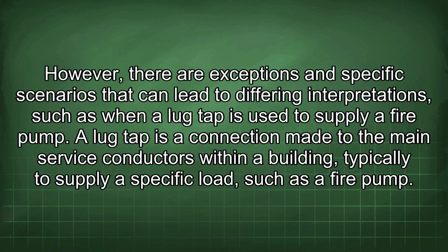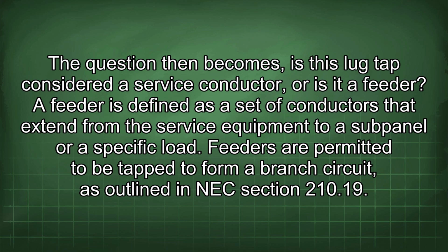However, there are exceptions and specific scenarios that can lead to differing interpretations, such as when a lug tap is used to supply a fire pump. A lug tap is a connection made to the main service conductors within a building, typically to supply a specific load, such as a fire pump. The question then becomes, is this lug tap considered a service conductor, or is it a feeder?